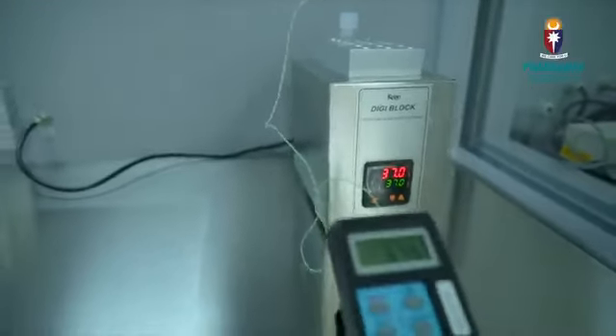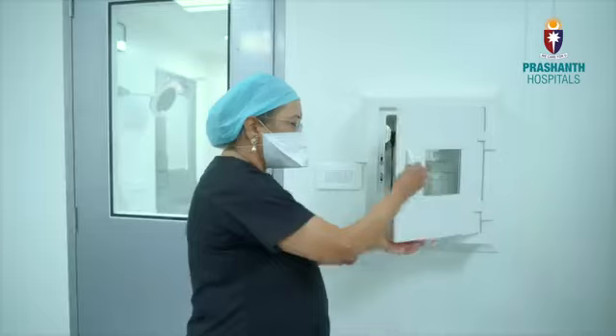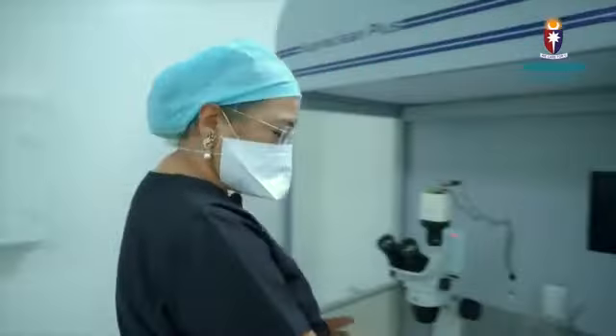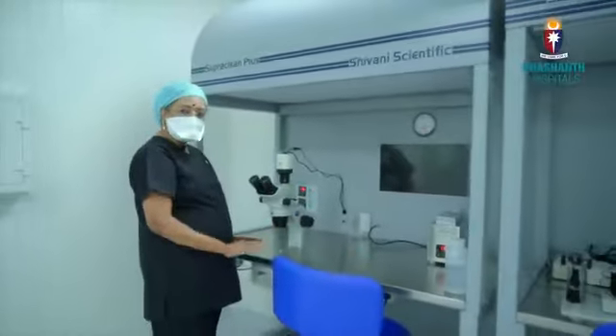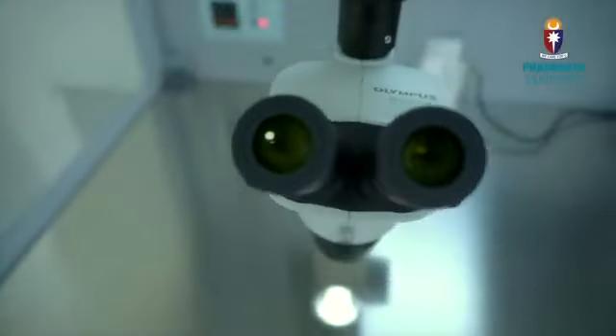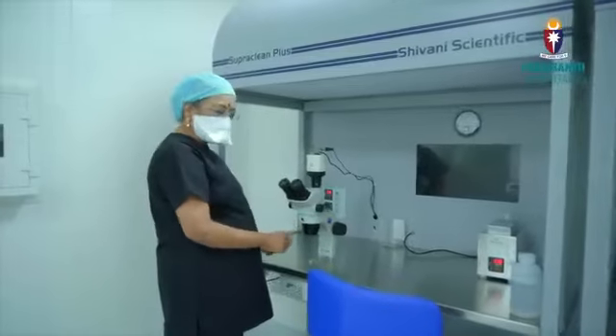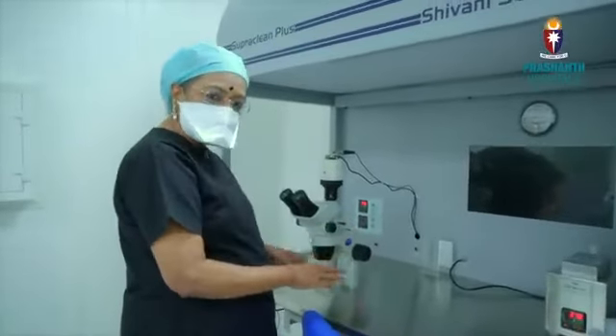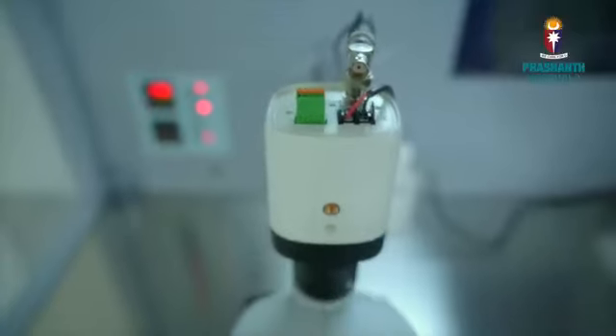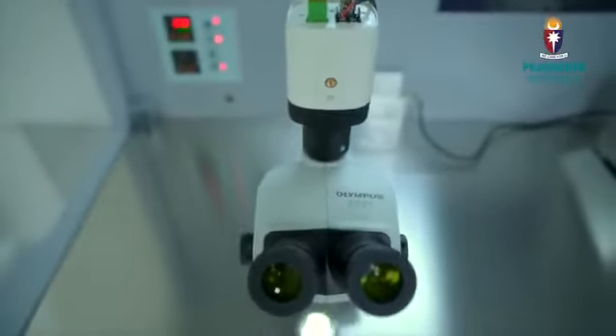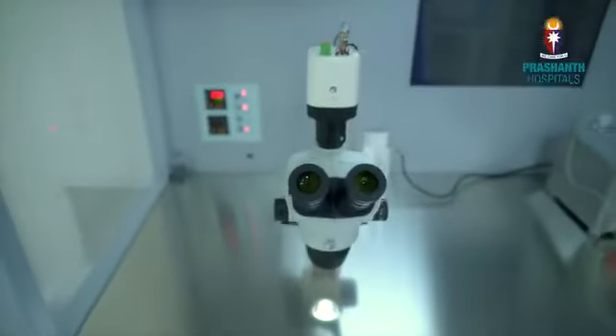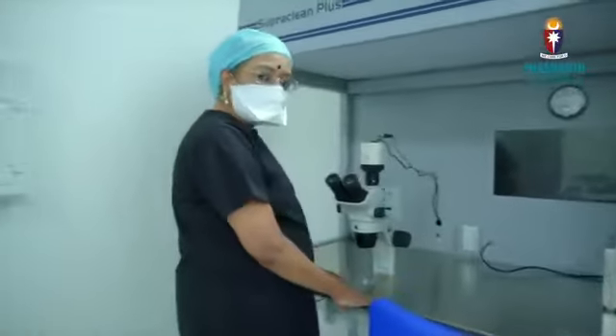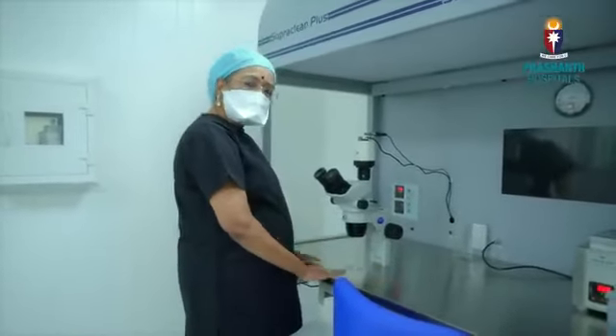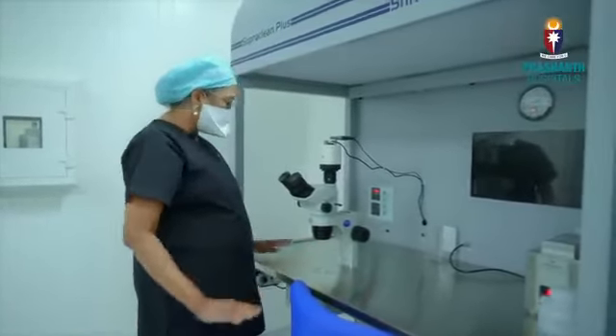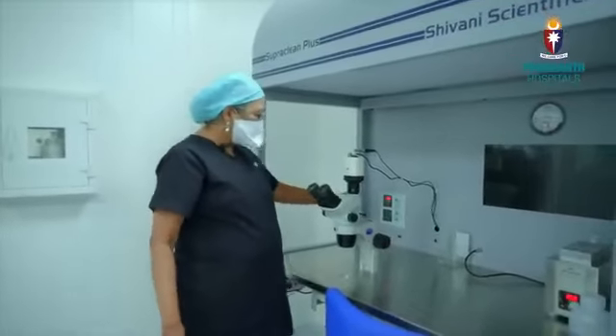The embryologist then picks up the tubes from there, and then he goes to the microscope. Now the microscope is a heated area. The entire thing is a laminar airflow which gives pure air and keeps pure air all the time, and the microscope, we use it to look at the eggs. So this is the microscope with which we look at the eggs, and once the tubes are there, they are kept in this digiblock so that the tubes are maintained at 37 all the time, and even when we keep the dish here, the dish should be at 37. So this entire thing is all heated once again. So this is a heated laminar airflow, and you look at the displays all the time. When you look at the oxygen, carbon dioxide, the temperature, everything is recorded there.